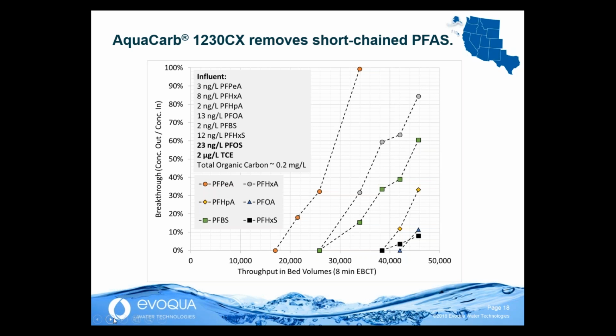Important here also is the total organic carbon content, which is quite low at 0.2 milligrams per liter, which means that competition with background organics is not too severe in this case.